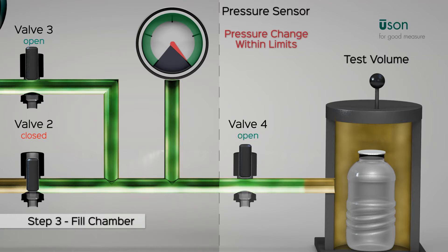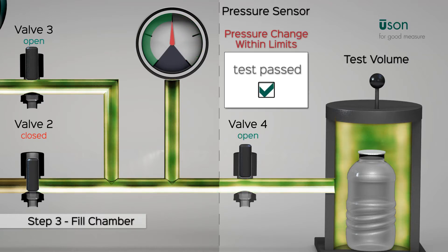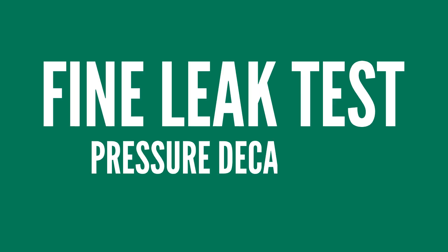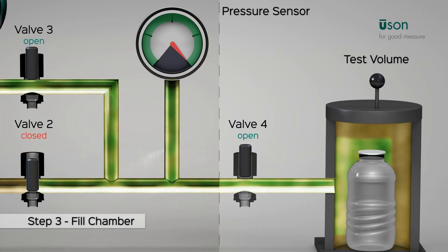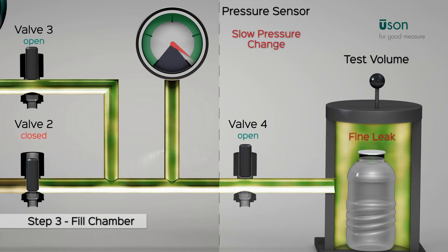This is where the fine decay leak test comes into play. The fine decay leak test is performed with a pressure decay test. As shown in this animation, the stabilize and measure steps allow for measuring a slow decrease in pressure over a pre-specified amount of time based on the application requirements. A slow drop in pressure below acceptable limits indicates a fine leak.